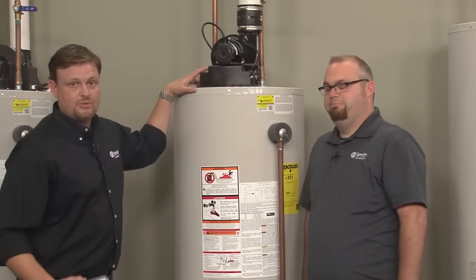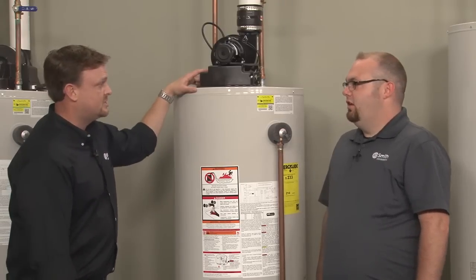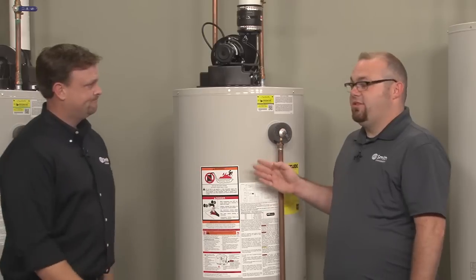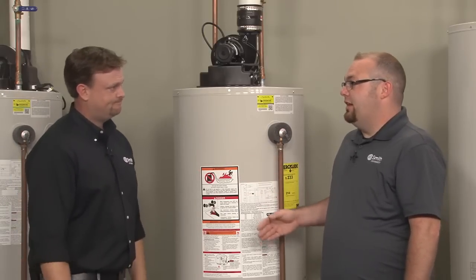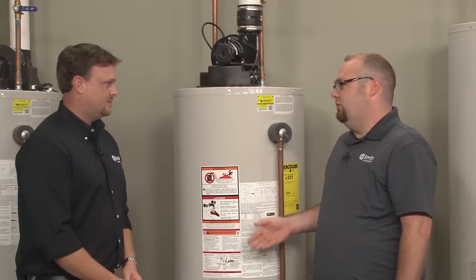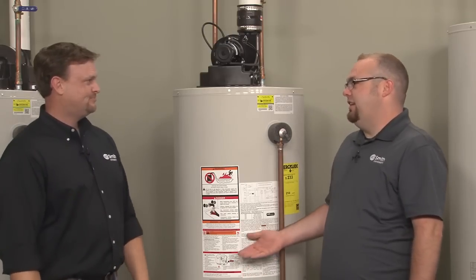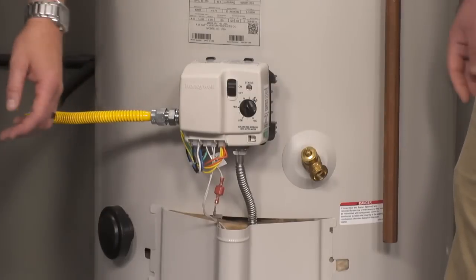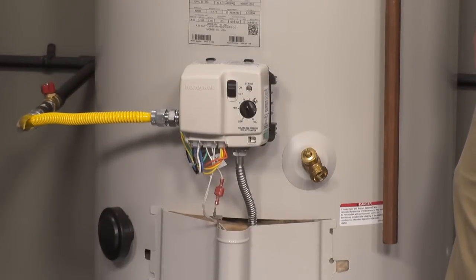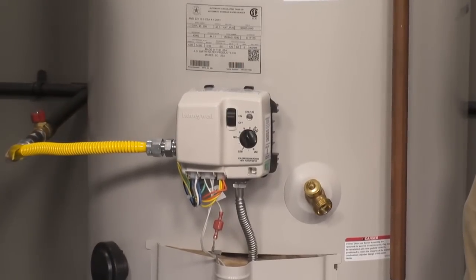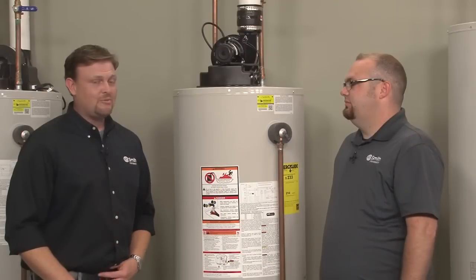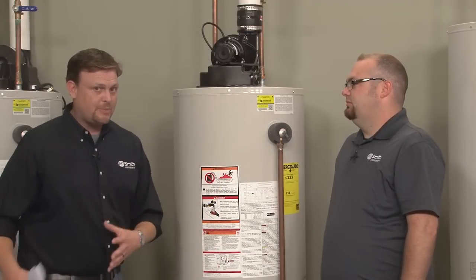The blower continues to run for a few seconds, and then it goes into standby. Correct. And anywhere it stops in that sequence of operation, that's when you're going to display a code. Yes. That's when we're going to get a status light or error light saying something's wrong. It's funny you should mention that, because that's what I want to talk about next: troubleshooting. And really, understanding the sequence is going to help you with troubleshooting.